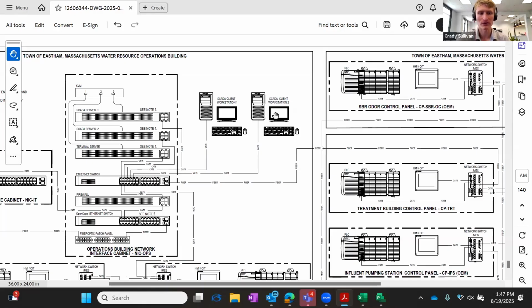The second form of redundancy is in terms of the SCADA failover. We have physical hardware - SCADA server 1, SCADA server 2 - but there's also virtual machines on each one, basically simulating that SCADA server software. So we'll have backups of those as well that we could always pull up if something were to go wrong with the initial instance. And there's redundancy between them - SCADA server 1 and 2 are sharing their database and all that information back and forth. Same thing with the historization.